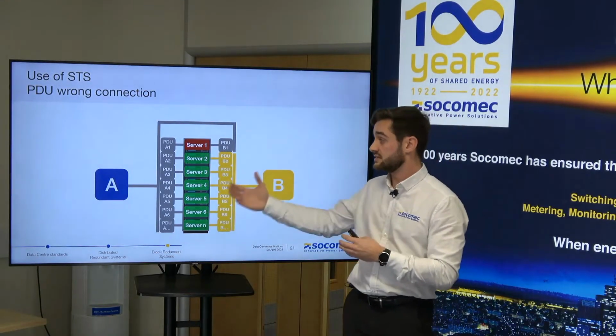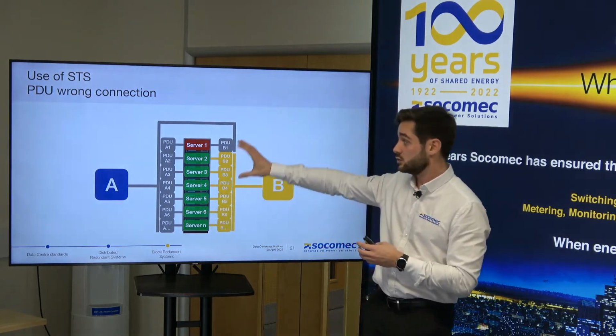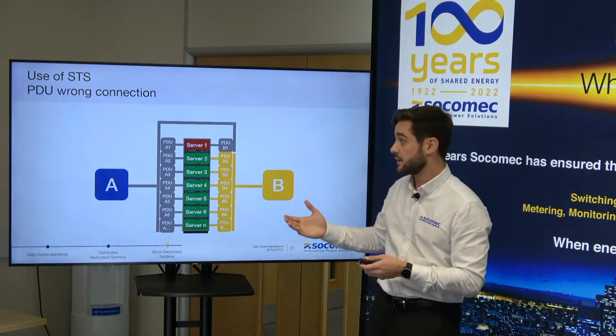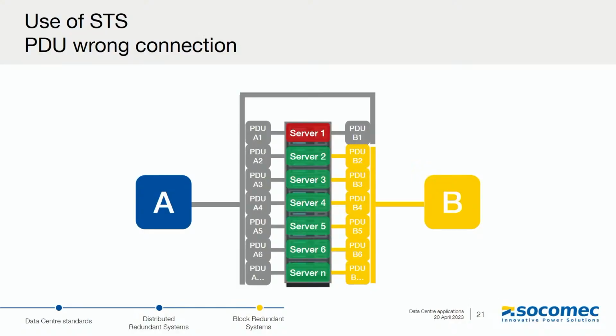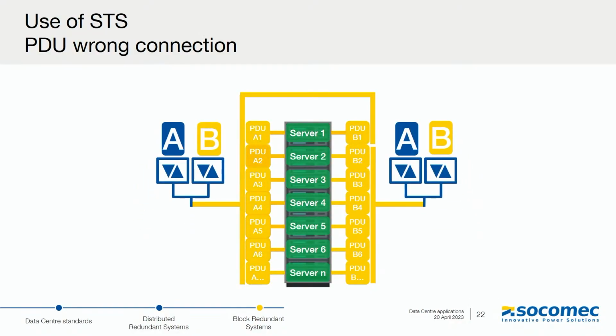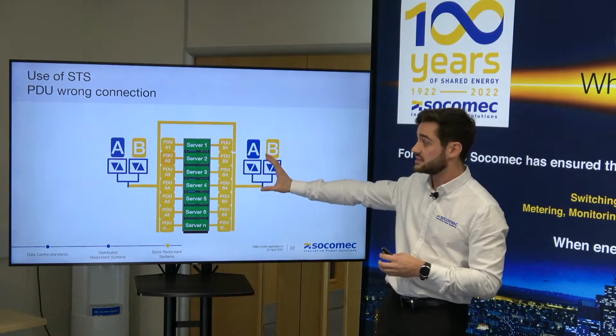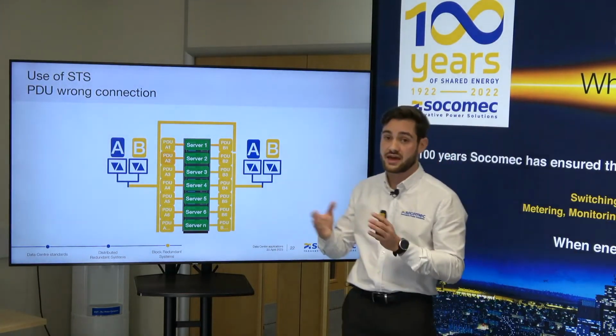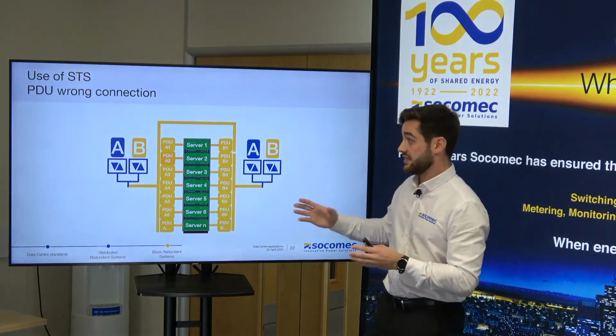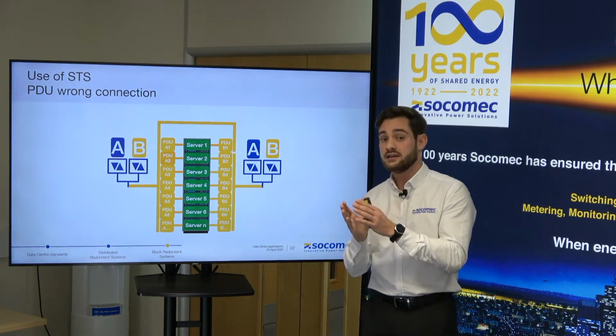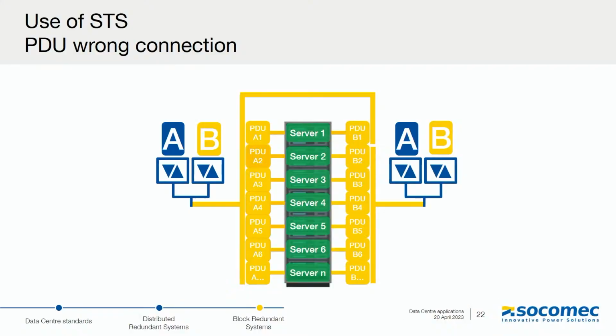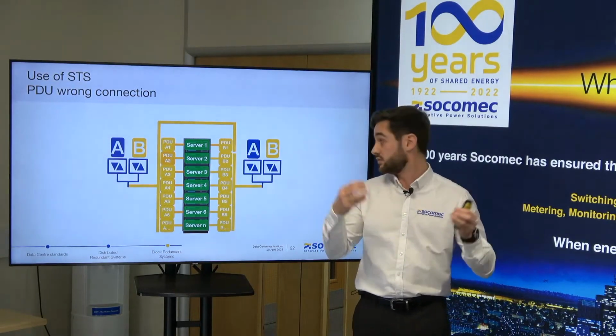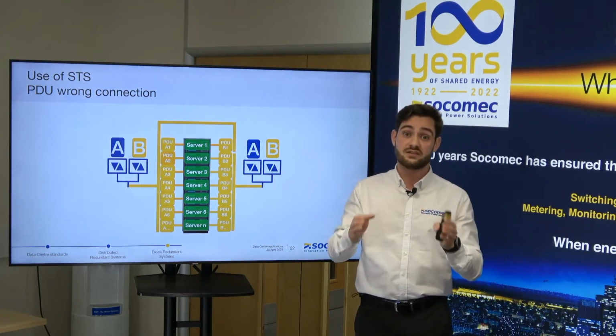Exactly the same result. So let's say power supply A is failing, then you would lose the power supply and then you would drop the load and drop the server. So to avoid that, the installation of STS will actually allow you to get 2 power supplies connected to the power distribution unit all the time. So if there is any failure, imagine in that specific case we had a failure again from power path A, so UPS system A, then the STS will switch to power supply B. And as you can see, all the power distribution units will be fed via this UPS system B. And the result is that all the dual corded servers will be fed via the UPS system B, but still 50% on each leg.